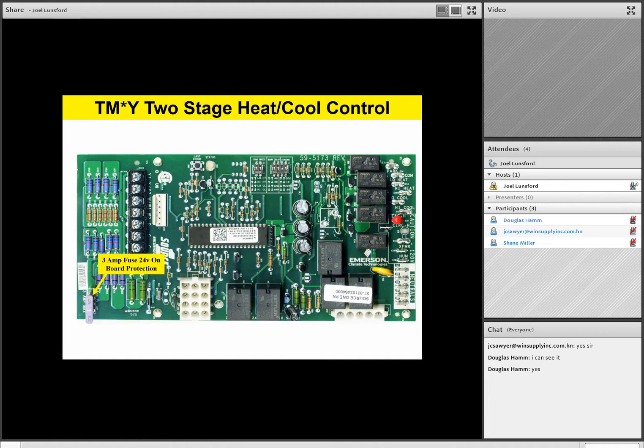Now please notice, team, right in the middle of this board on the right-hand side, more towards the middle of the board, is our flame current pad on this particular board. That flame current pad, you'll notice that 1 volt DC will equal 1 microamp DC flame current for testing purposes. Okay, any questions or comments on the TMY control board that we have with a high efficiency ECM motor? Any questions or comments on the layout of this board?